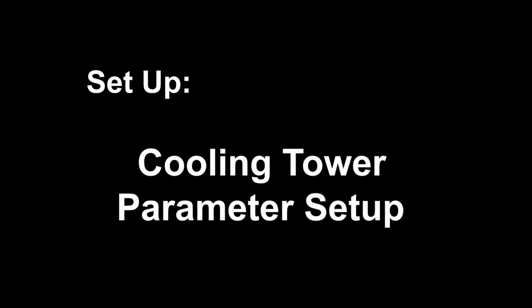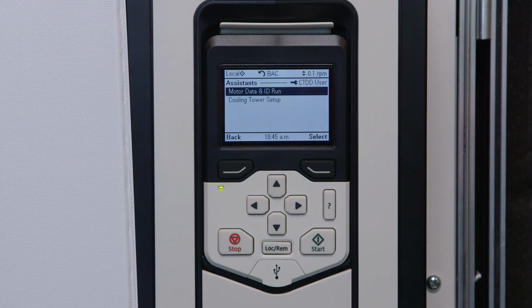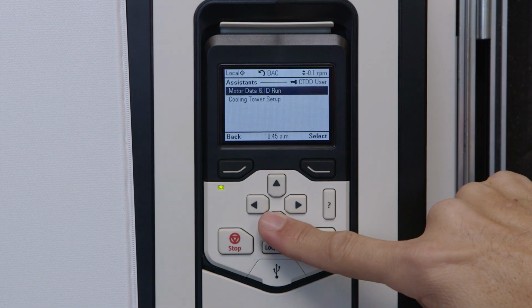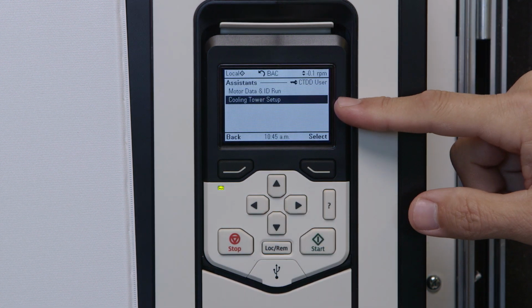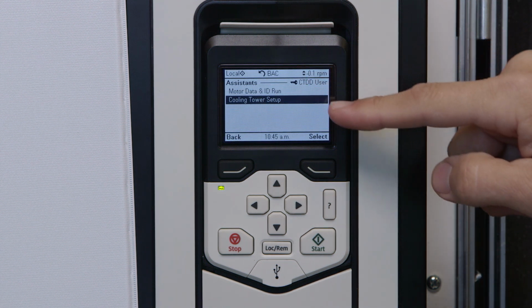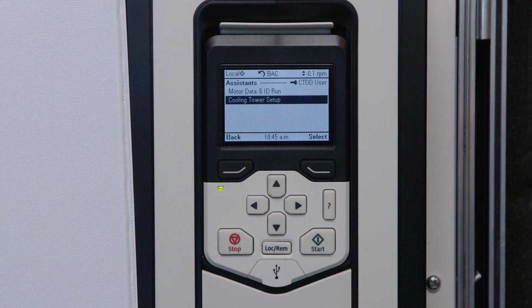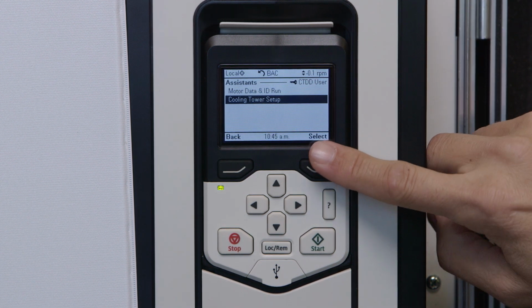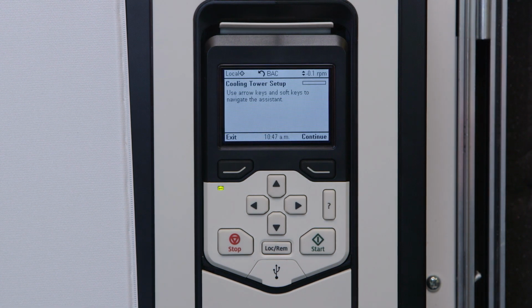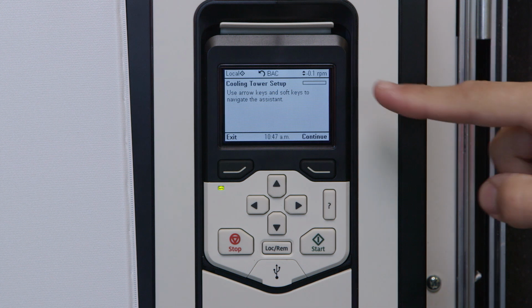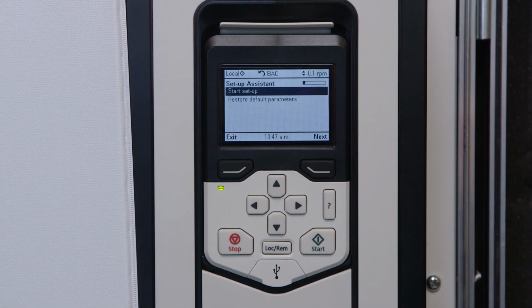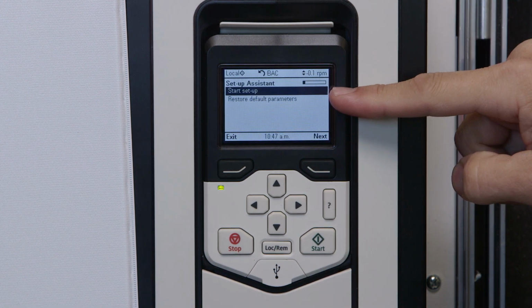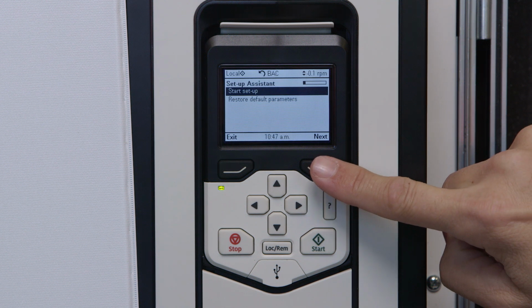Cooling tower parameter setup. Now, let's set up the cooling tower parameters in the VFD. From the Assistants display, scroll down to where it reads Cooling Tower Setup. Then press Select. At the Cooling Tower Setup screen, press Continue. You will now see the option that reads Start Setup. Select this option and press Next.